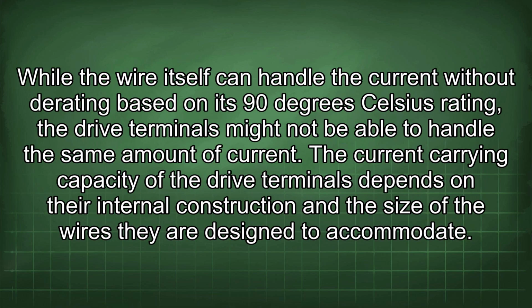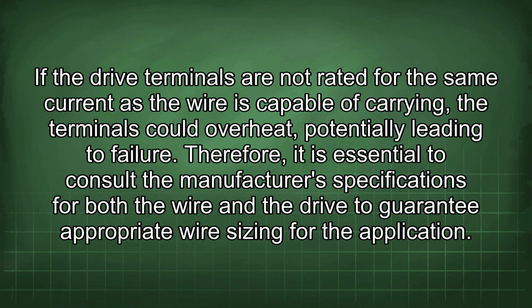While the wire itself can handle the current without derating based on its 90 degrees Celsius rating, the drive terminals might not be able to handle the same amount of current. The current carrying capacity of the drive terminals depends on their internal construction and the size of the wires they are designed to accommodate. If the drive terminals are not rated for the same current as the wire is capable of carrying, the terminals could overheat, potentially leading to failure. Therefore, it is essential to consult the manufacturer's specifications for both the wire and the drive to guarantee appropriate wire sizing for the application.